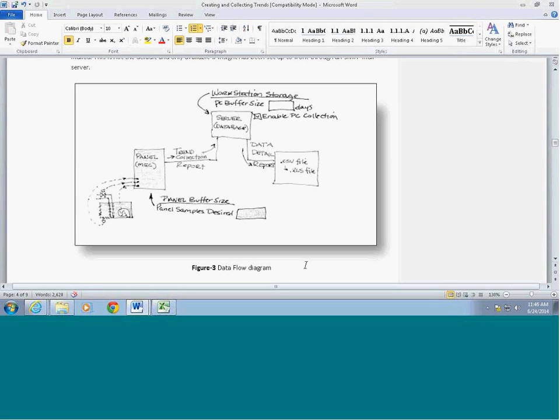So we have a collection. It takes a certain amount of time to get all that data off these networks and get it into the server. And if you run this report too soon, and you try to pull it from here, it hasn't had time to make it here, then you get an incomplete CSV. So the solution is to allow enough time to pass when you schedule this report to run.